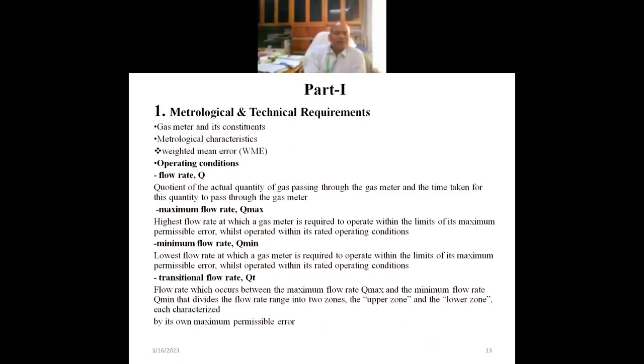And maximum flow rate Q maximum is the highest flow rate, and minimum flow rate is the lowest flow rate. And transitional flow rate is denoted by QT. It is the flow rate which occurs between the maximum flow rate, that is Q max, and the minimum flow rate Q minimum, that divides the flow rate range into two zones, the upper zone and the lower zone, each characterized by its own maximum permissible error. So the upper zone has its own maximum permissible error, and the lower zone also has its own maximum permissible error.